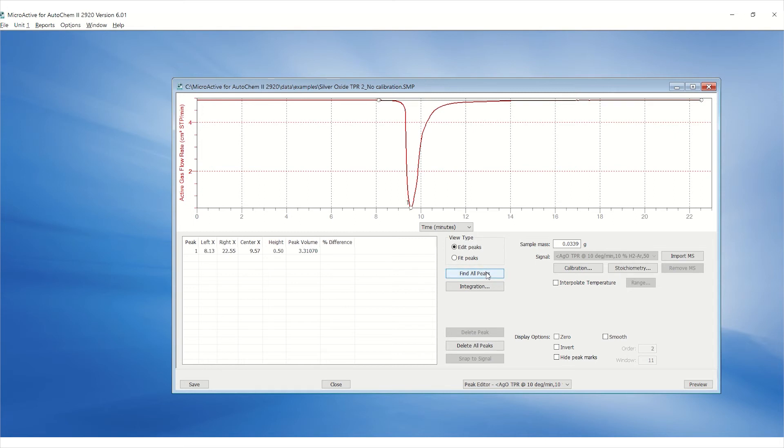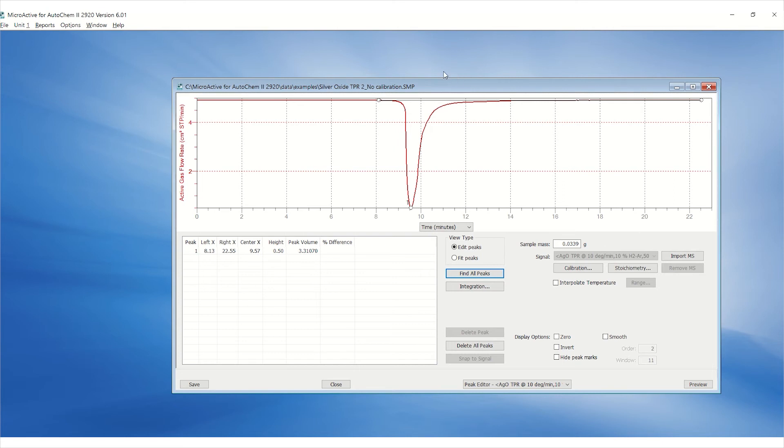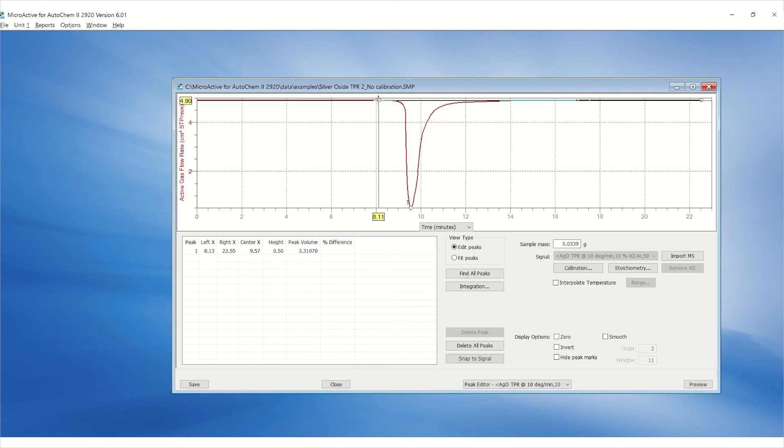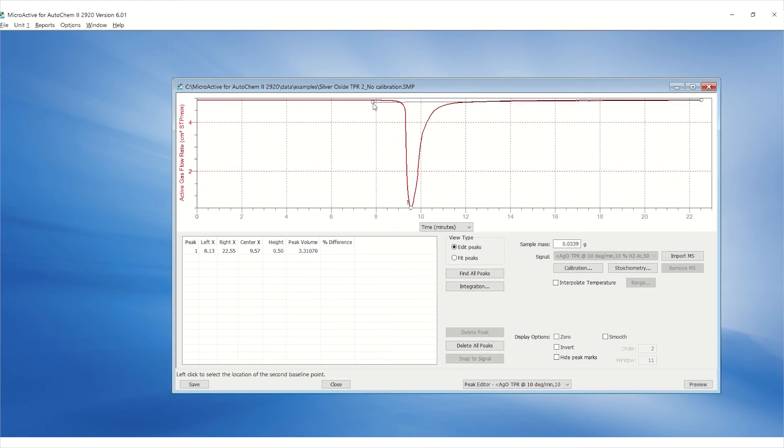Automated peak integration may need further edits. To adjust the position of the peak integration, hover over the circle and once the cursor is turned to a cross, double click on the circle. This will allow the circle to be repositioned.